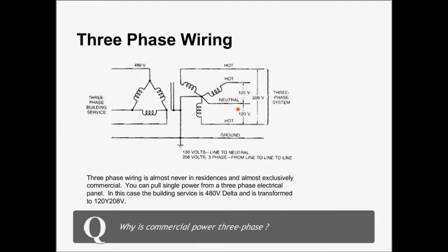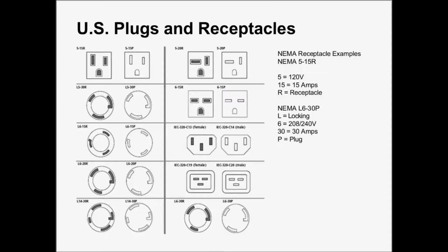And this is actually called 120Y208. And it's the same situation here, where if you could imagine this being the electrical panel, you would put a breaker in from hot to neutral, you would get 120 volts. And if you put the breaker in hot to hot, you would get 208 volts. So again, it's the same thing, but this is really more just for familiarity.